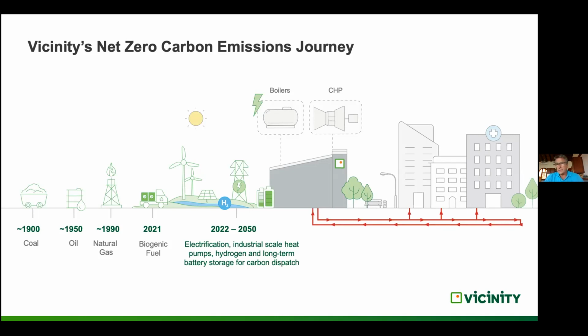So the front end of the plant has changed over time. Many of these legacy districts, big urban core districts, were built back in the day, and they were coal-fired. Then in the 50s, it went to oil-fired. In the 1990 timeframe, that era, many converted to gas. And in our case, we then converted to combined heat and power with gas. So there's a long history of basically changing out the front end, the primary fuel source, as time changes. So that's where we are -- we're at that next inflection point to figure out how we swap out that primary fuel source so that we can decarbonize rapidly.